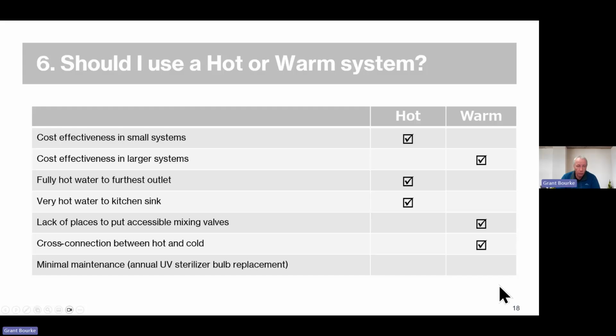In the warm water system, we've got to change the bulb every year. So in a big building, that's not a big deal. But in a small building, you don't have to do that with a hot water system. So it might be more beneficial in a smaller building to have a hot water system. So there's the pros and cons. It'll vary from project to project, but they're the things that you might need to bear in mind when you're considering whether you want to use the hot water system or the warm water system. The hot water system's simpler if you're doing a largish house and you're having a crack at it for the first time.